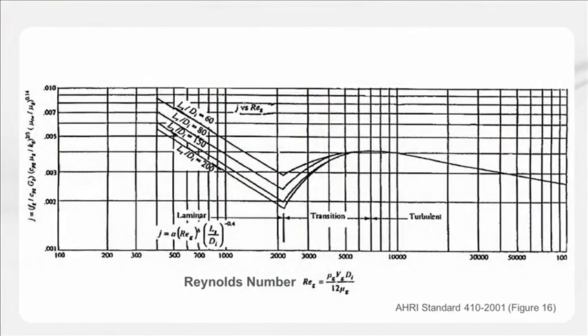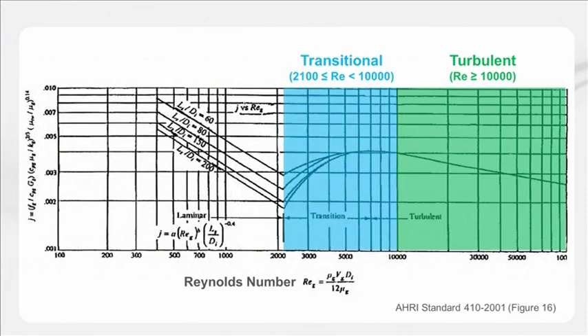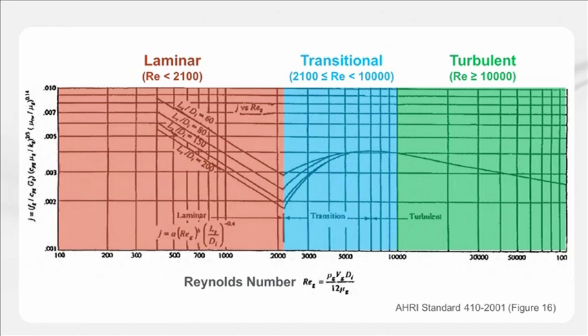There are three distinct regions of flow turbulence: fully developed turbulent flow, transitional, and laminar. When the Reynolds number is above 10,000, the flow is turbulent. Between 2,100 and 10,000, it's considered transitional. When below 2,100, the flow is laminar. Right at the point where flow changes from transitional to laminar is where the heat transfer coefficient bottoms out. As the Reynolds number decreases below this point, the length and diameter of the coil tubes plays an important role in accurately determining heat transfer performance.